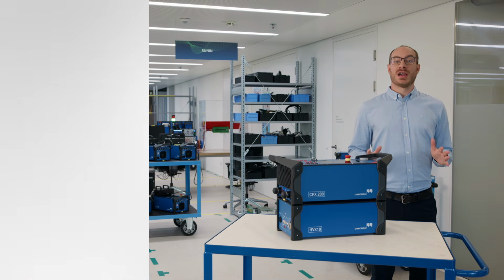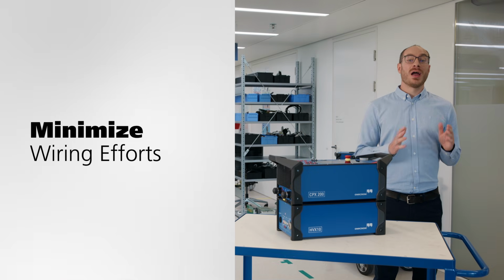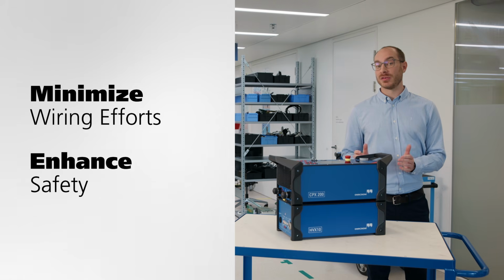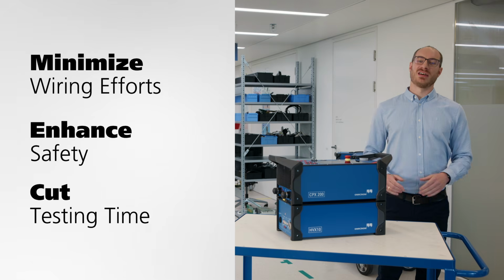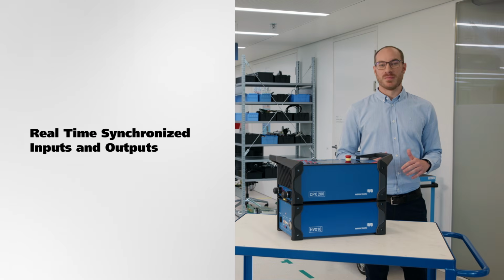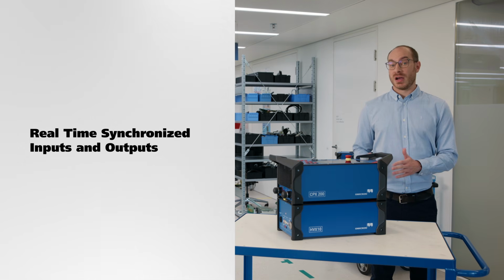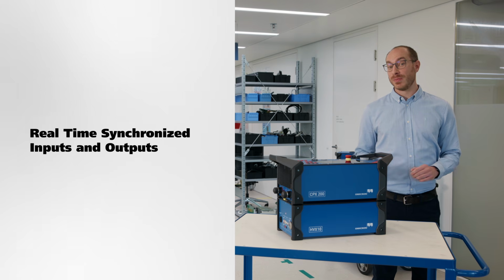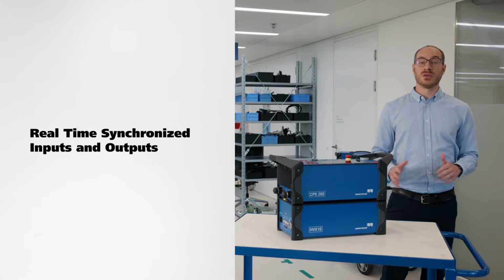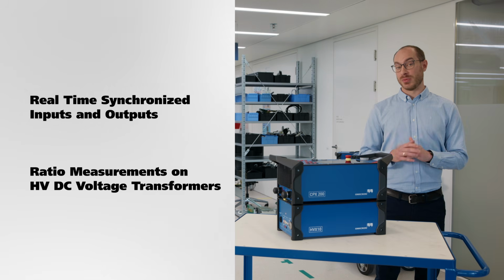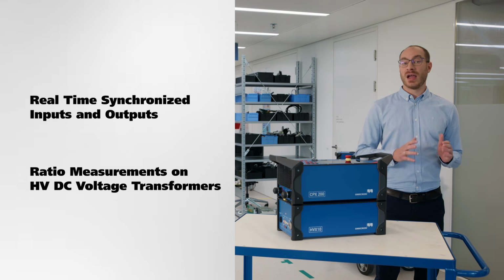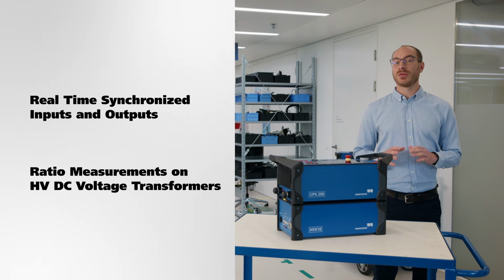All these innovations help minimize wiring efforts on site, enhance safety by reducing the number of ladder trips, and significantly cut testing time. But the HVX 10 is far more than a diagnostic insulation device. What really makes the HVX 10 stand out is its adaptability. For example, all its outputs and inputs are synchronized in real time with the CPX 200. This allows you to explore entirely new application possibilities, such as testing HVDC voltage transformers with ratio measurements.